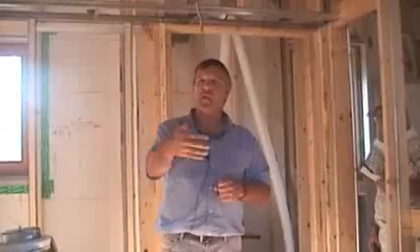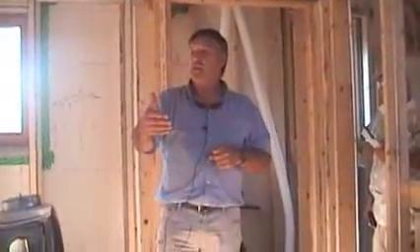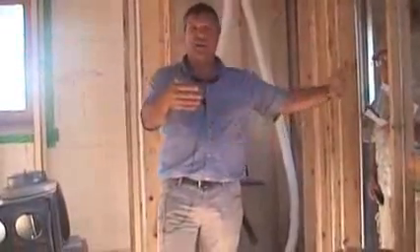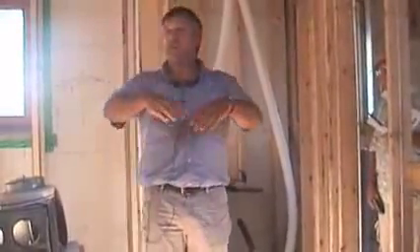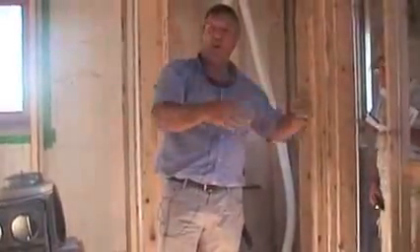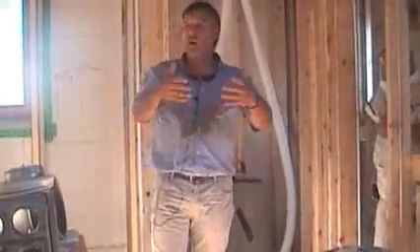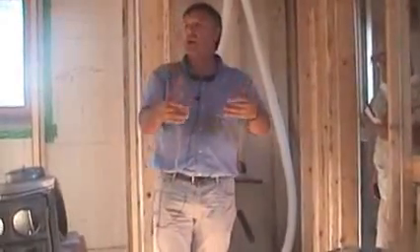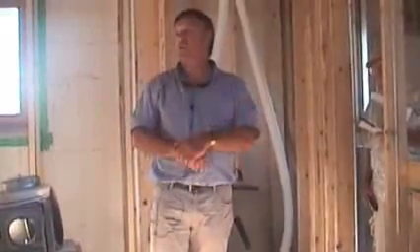So it knows that the air coming out of the house is above 75. It gets up to 80 during the day, and that's 80 degrees going this way. And it knows that the air coming in is below that. A damper opens, bypasses that warm air around the core, and now the air comes through the filters and directly into the house. So when it gets down into the 60s at night, that's cool night air coming directly in and helping to cool the house.